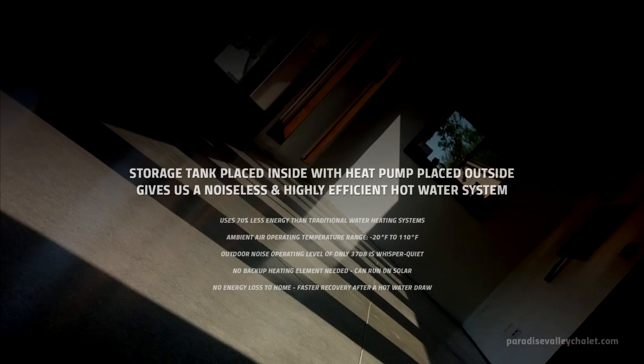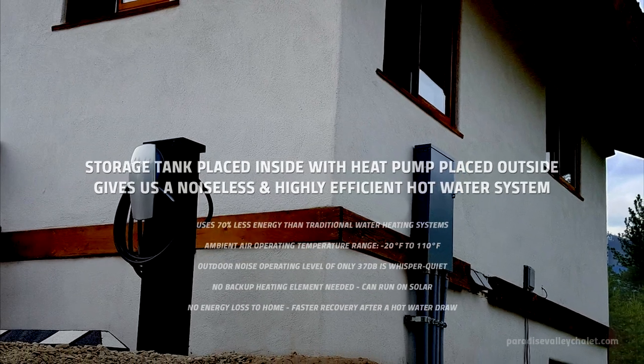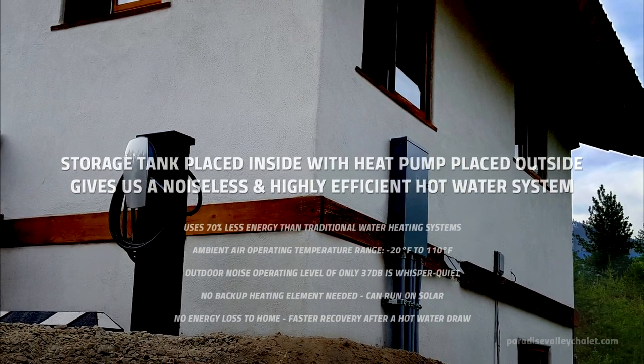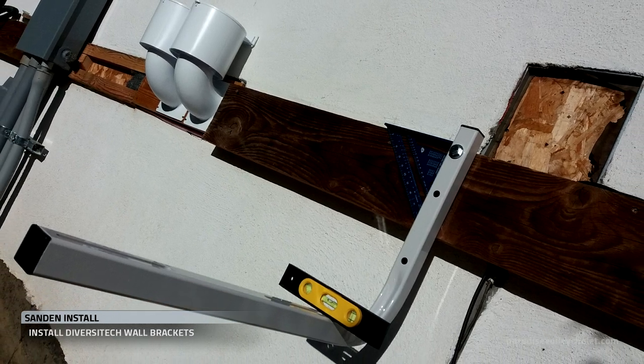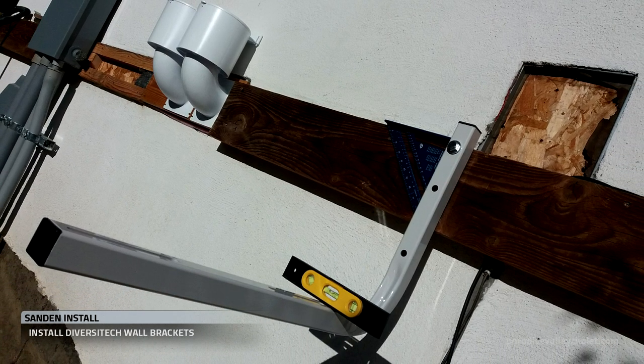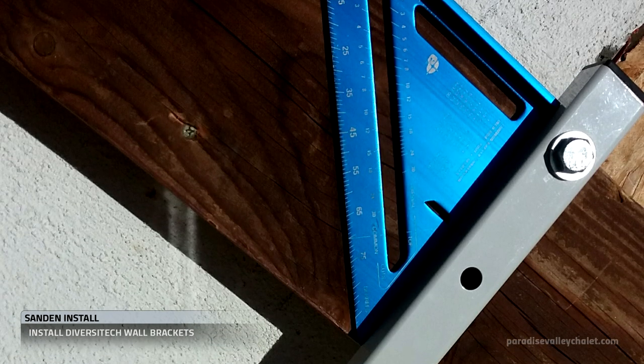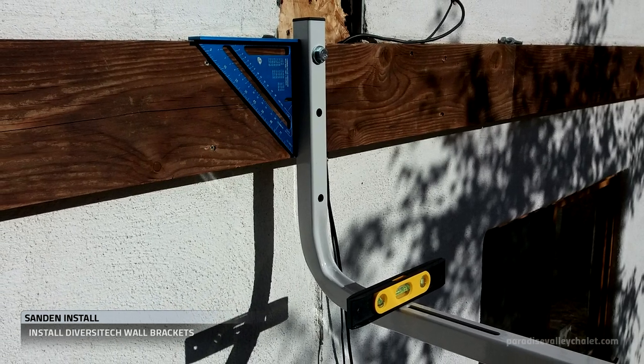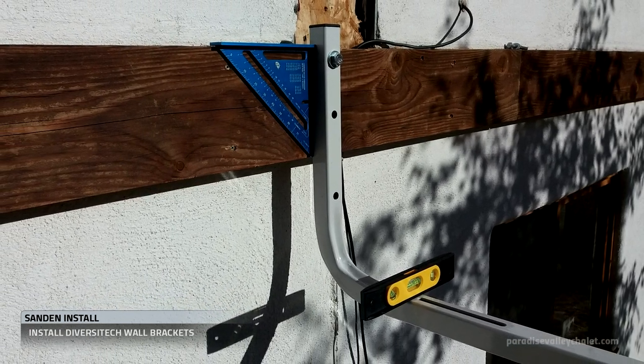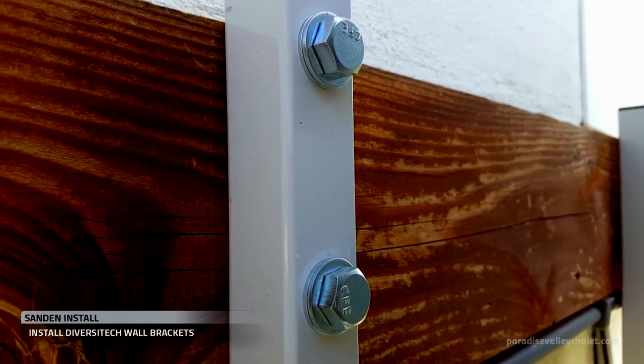We've chosen to install the tank on the lower level of the chalet and mount the heat pump on L-brackets on the side of the building. So first we're mounting these 500-pound rated Diversitech Quick Sling L-brackets on the side of the building. These brackets can be mounted on concrete, wood, or other surfaces. Using half-inch bolts and washers on both sides, we're securing the brackets to the building.